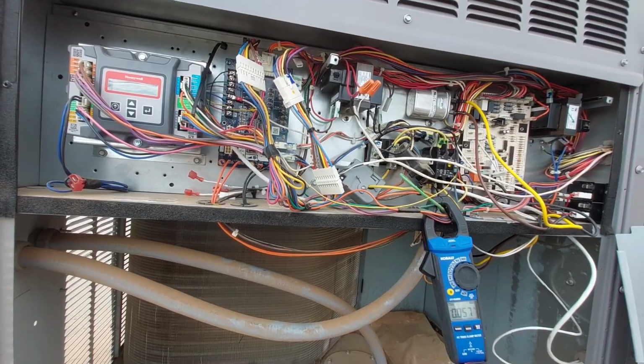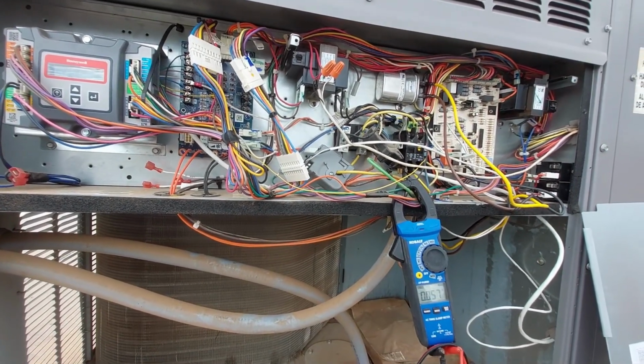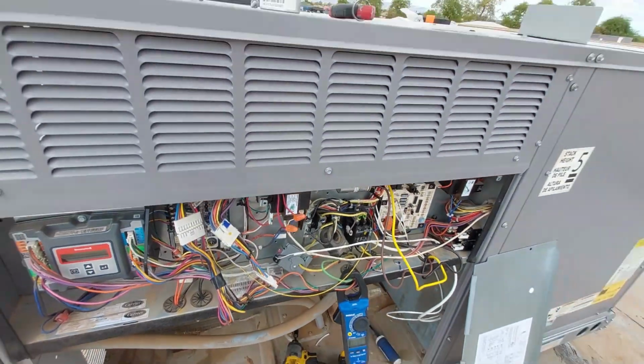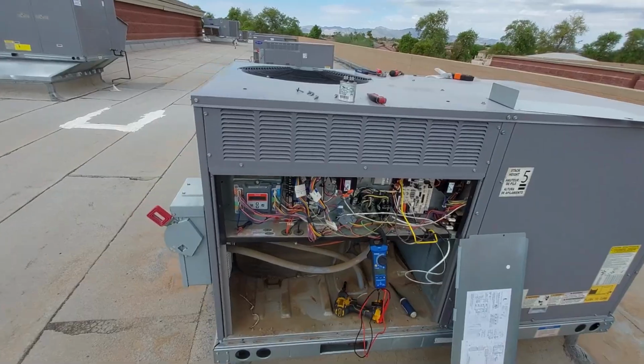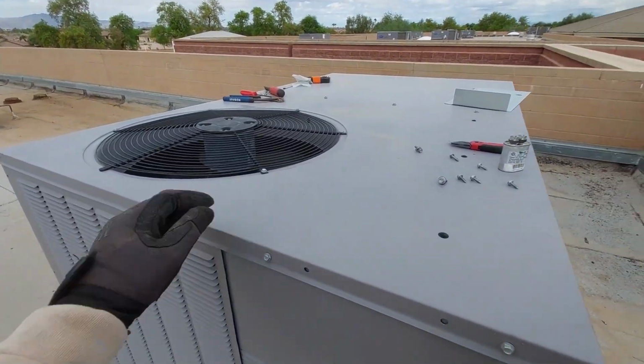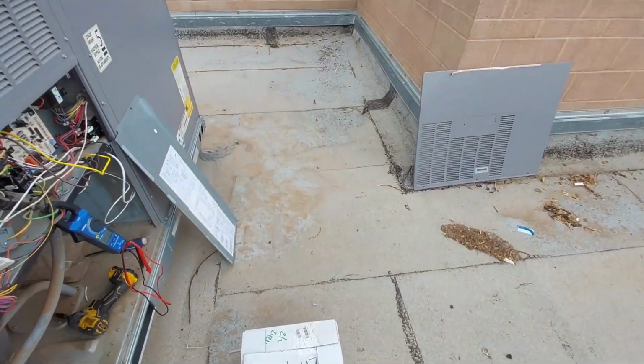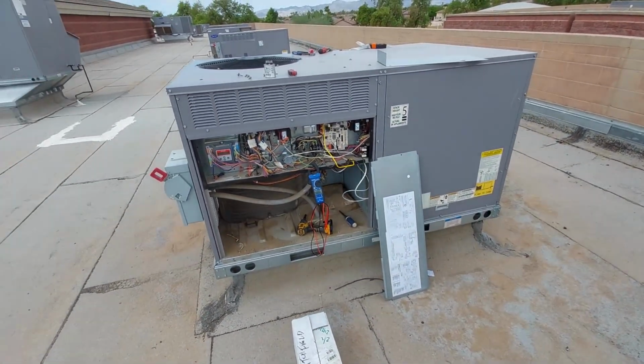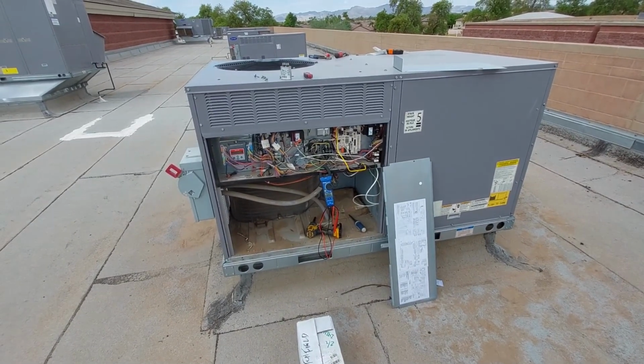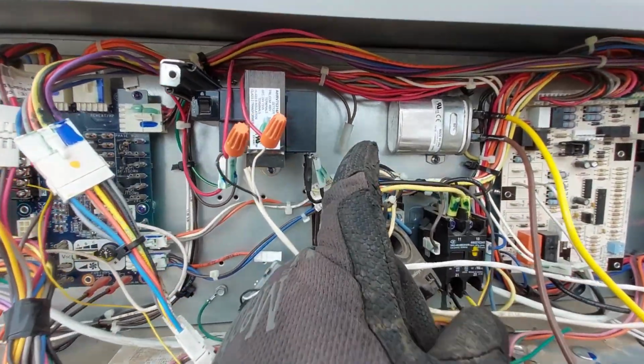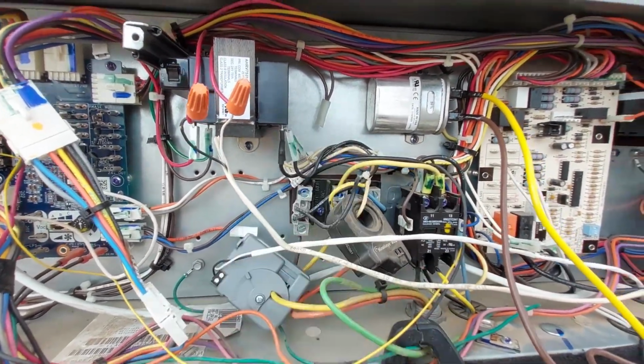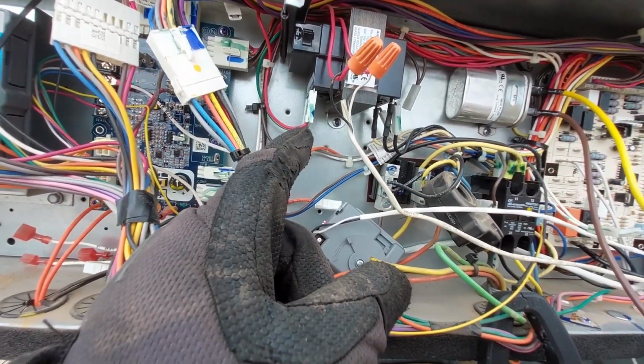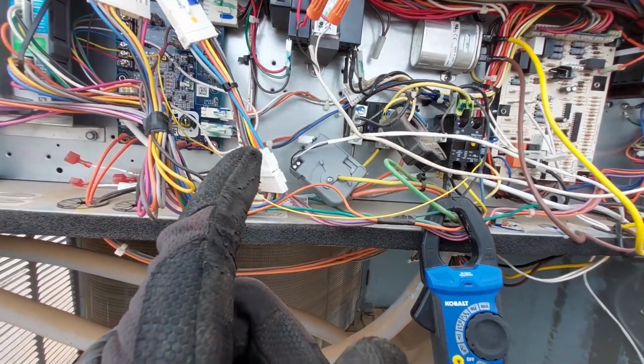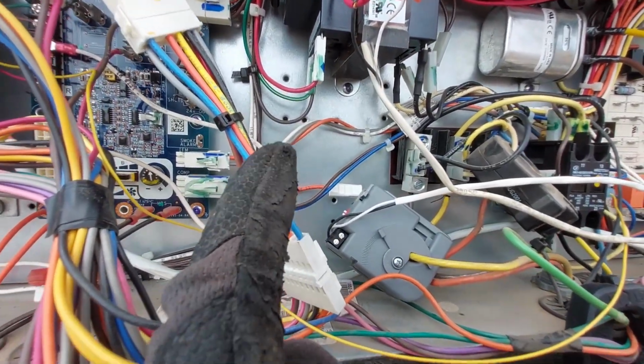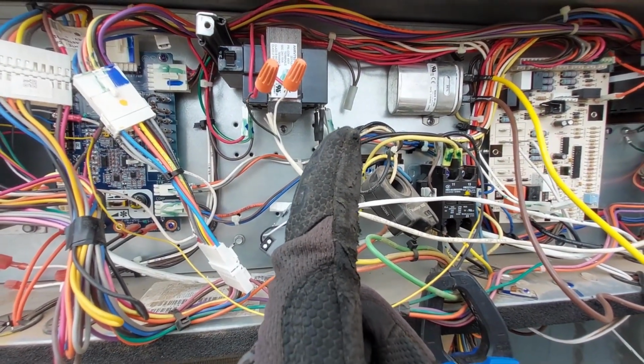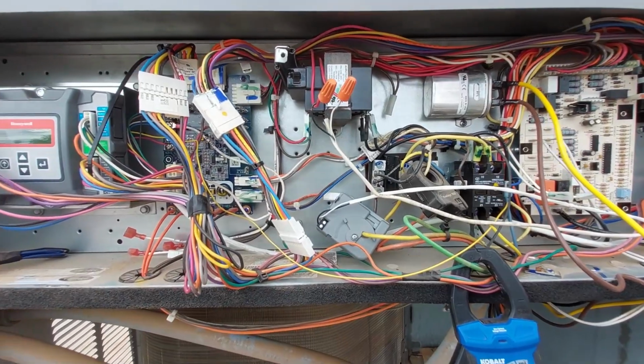Yeah, I think I'm gonna call dispatch and let them know I'm at a dead end here, and see if they could send someone else out with a little more experience. Maybe I could get on the phone with them and they could explain what they did and how they did it. Another thing I noticed was these two brown wires here just kind of dangling, not connected to anything. I thought they would be connected to the low voltage side on this transformer, but I checked the schematic, and off of this transformer it should be that brown and green wire. So this is correct, but I don't know where this brown wire goes to, right here. So I'm kind of at a dead end.